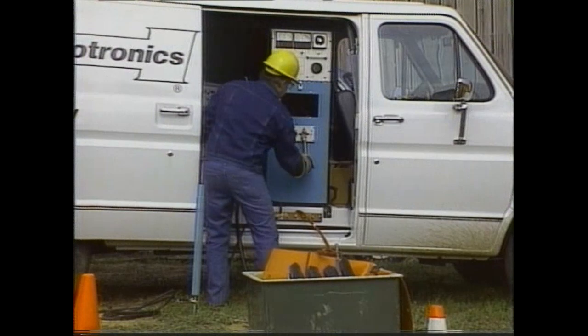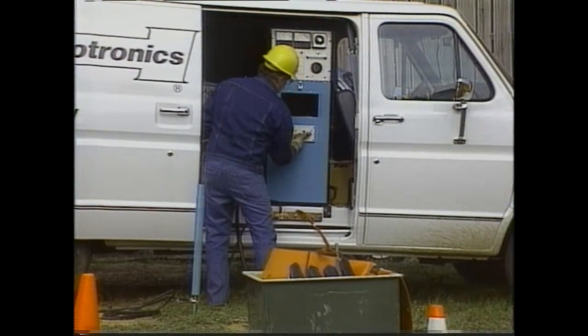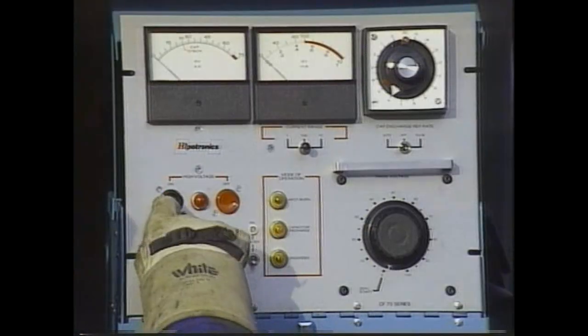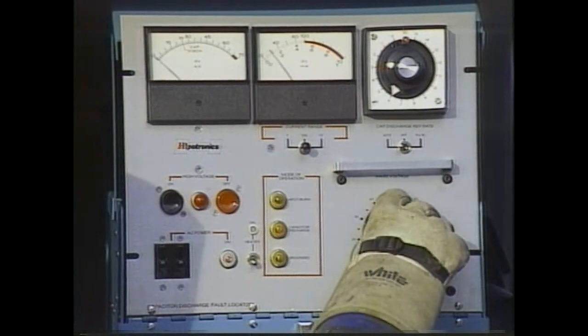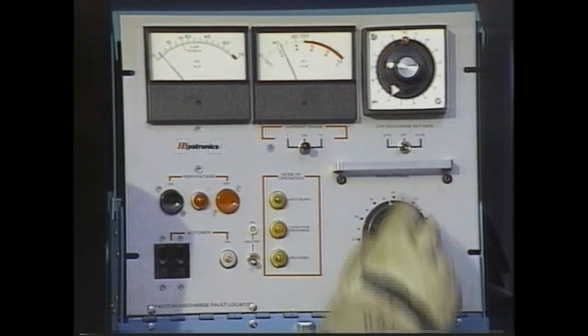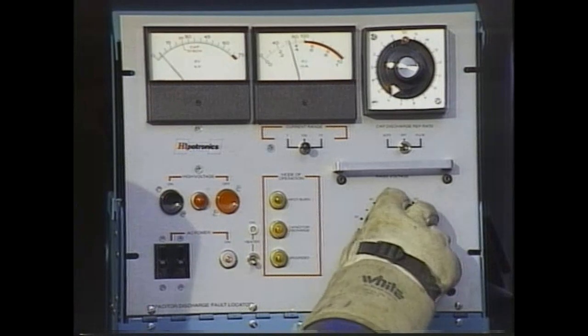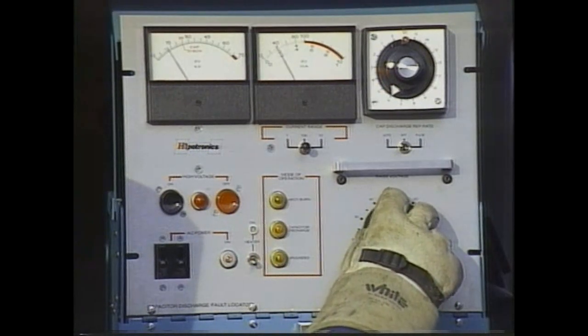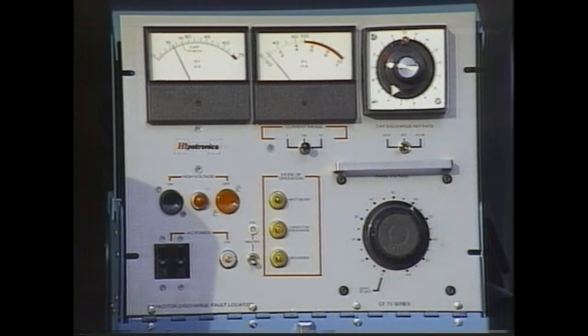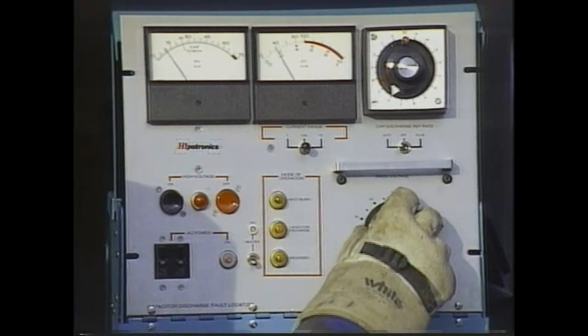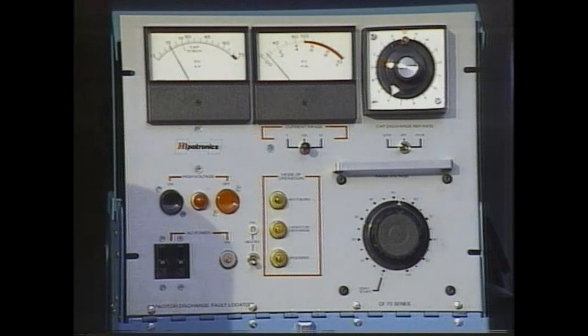The current meter jumps up scale, showing us that the capacitor is charging. As the capacitor comes up to the voltage we have set, it will draw less current, so we see the current meter starting to reduce. When the timer trips, the thumper dumps its stored energy into the cable, and we have a thump. With the thump established, I'm going to use a directional acoustic detector to locate the fault.